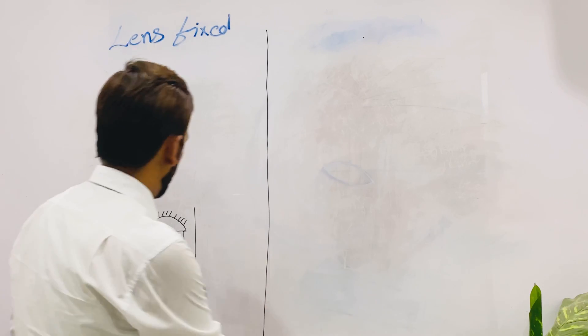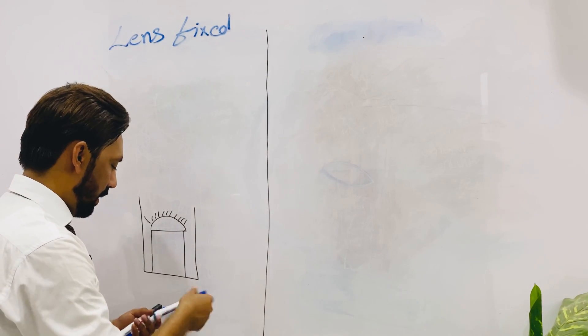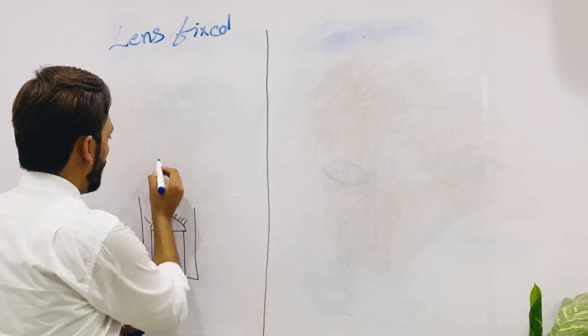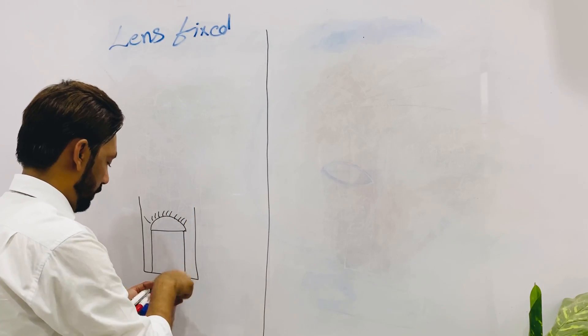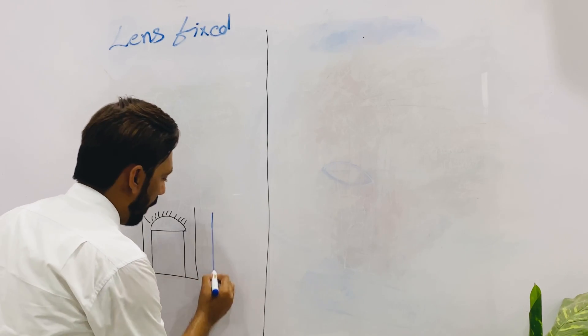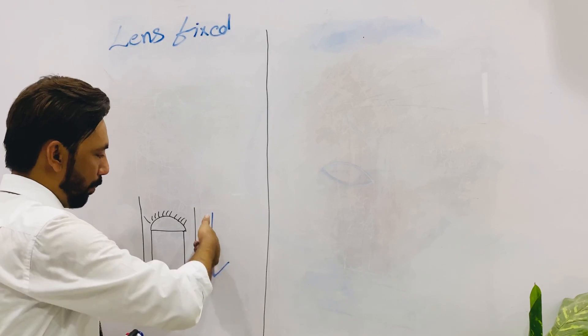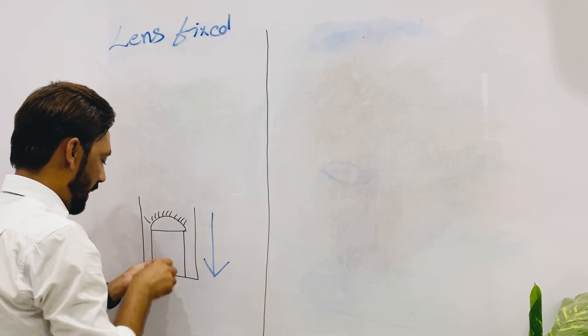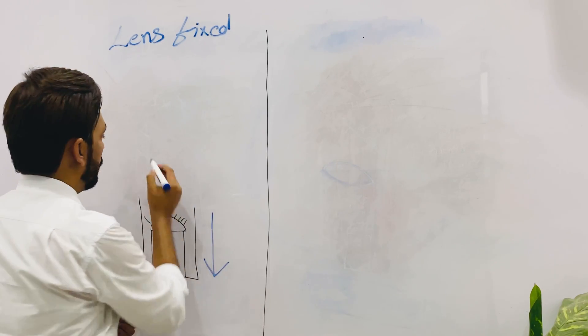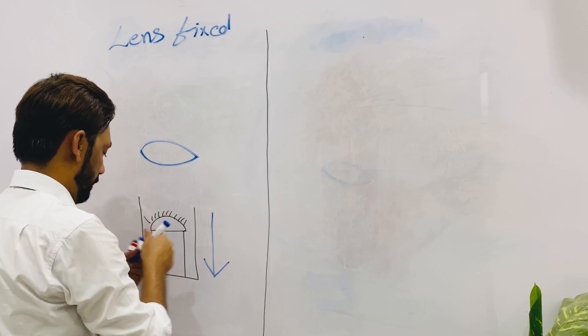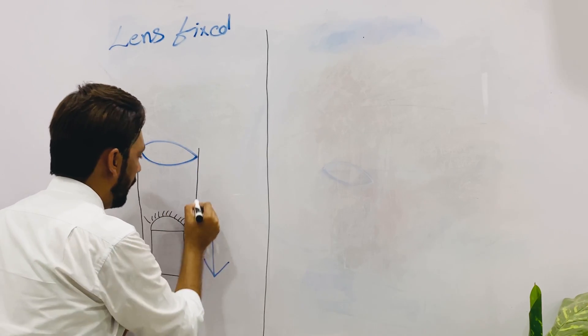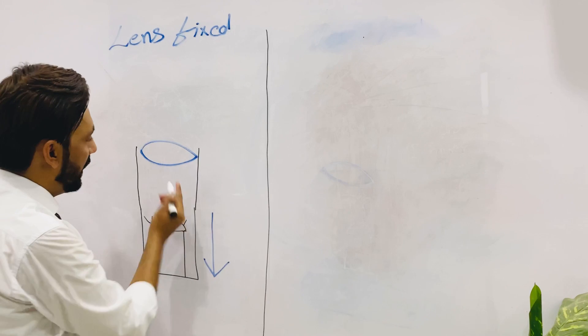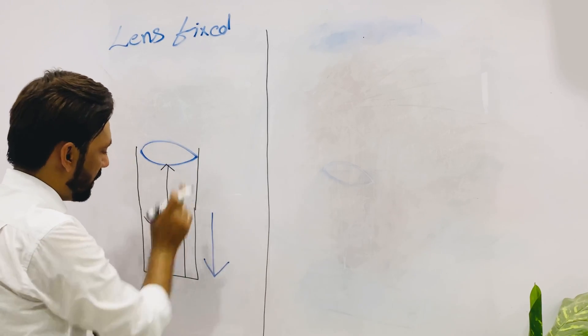In this type of retinoscope, this is the bulb or the light source. This bulb is movable, and when the sleeve is down, the bulb will go down. The condensing lens is fixed, so it stays in place. When we pull the sleeve down, the bulb moves down, creating a greater distance between the condensing lens and the bulb.